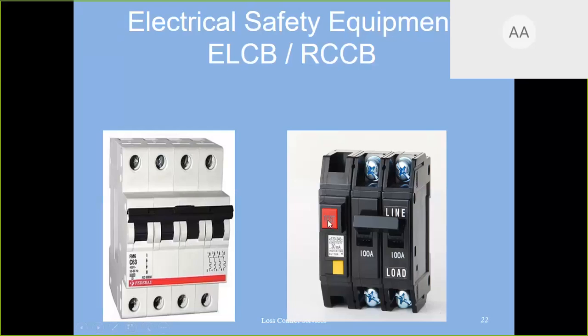So we have ELCB for 100 milliampere. We have very sensitive 50 milliampere, and we have for 200 milliampere also. So if ELCB is installed at each distribution board, it will trip before anybody gets electrocuted. There will be no electrocution because there will be no current leakage more than 50 milliampere which can pass through a human body. So this is also a must that everybody should have either ELCB or RCCB. This is earth leakage and this is residual current circuit breaker. ELCB will trip at 50 milliampere; RCCB trips on the difference between how much current is going and how much current is coming back. If there is a gap between going and coming, it means something is leaking. It will trip. RCCB is more sensitive than ELCB, so it has some nuisance tripping also. So we install RCCB where there is very fine electronic equipment where I don't want any current leakage. There I install RCCB.